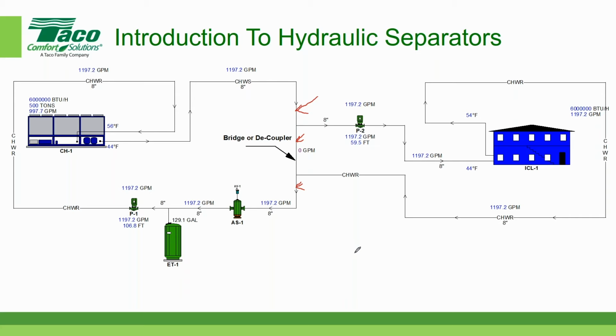All set for questions. Okay, so the next piece of the puzzle is what if we had flow both in the primary loop and the secondary loop. So we're all on the same page, the one on the left is primary, the one on the right is secondary. Let's assume that the flows are now equal, and I'm rounding this off, so I'm going to make this 1,200 gallons per minute. And this pump is also pumping 1,200 gallons. So that means the water is coming around the corner here at 1,200 gallons per minute.